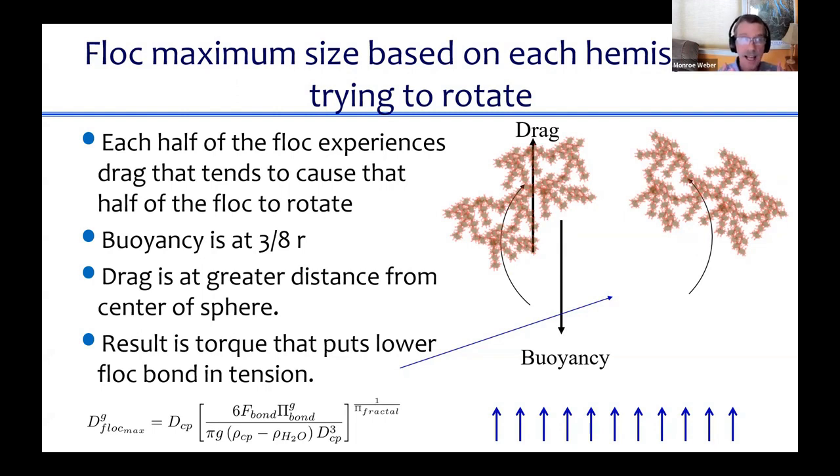And that maximum terminal velocity means that if you design a sedimentation tank where the upflow velocity is faster than the terminal velocity of the biggest flocks, then nothing will be in your flock filter and nothing will be able to get out of the plate settlers and down to the bottom of the sedimentation tank.